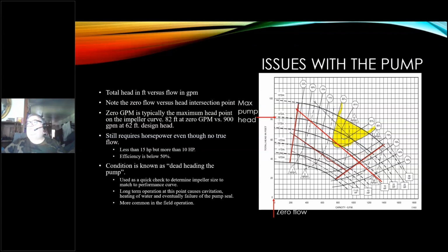0 GPM is typically the maximum head point on the impeller curve. 82 feet at 0 GPM versus 900 GPM at 62 feet. It still requires horsepower, even though there's no true flow. So that operating point falls in between 10 horsepower and 15 horsepower. I'm still using energy at zero flow.